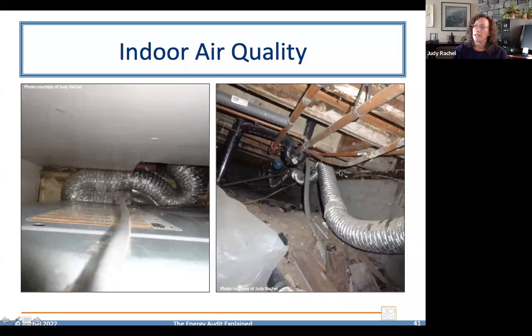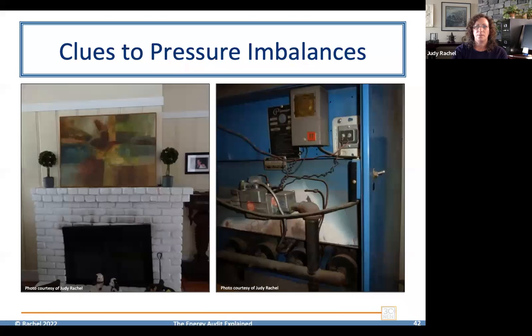This is how it snakes then through the crawl space itself with these great big P traps in it, and it's much too long of a run without a booster fan. So you just follow the clues all the way along so that you can figure out what your recommendations are. You need to figure out whether you can, first of all, straighten this out, shorten it up to the proper code lengths, and plumb this properly so that it doesn't have these large bends and is actually meeting our code rules. Can we find a different place to get the dryer combustion gases out of the house? Just all the discoveries that we need to be making.